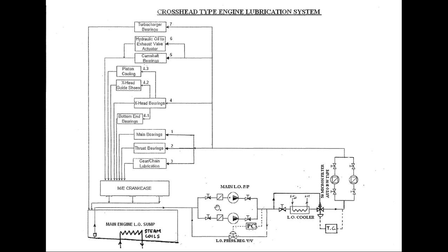The lube oil pump takes suction through suction filters. These filters have magnets to catch metallic debris caused by wear in the various moving parts of the engine. This debris is washed from the lubricated parts into the crankcase and finally into the lube oil sump. During suction filter cleaning, the metallic debris collected at the magnet should be checked — more debris means the rate of wear is high, and vice versa.